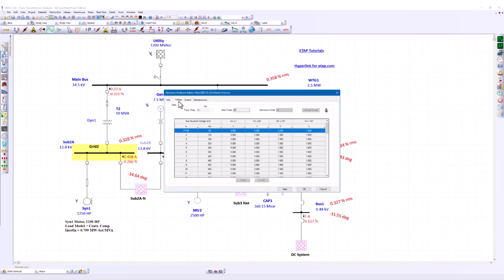The main content is in the voltage and current tabs. In the voltage tab, you will see the harmonic distortion limits are categorized based on different voltages. You can specify the voltage total harmonic distortion and also every individual harmonic distortion limit.